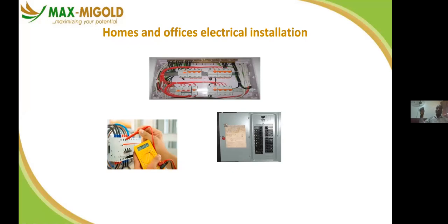And you see every breaker rated 5 amps, 10 amps, 32 amps, 50 amps, and so on. It also helps you not to overload a certain breaker. If you know the power rating of your appliance, like your electric kettle or your cooker in the kitchen, you cannot go on, maybe it's 50 amps. So you see 25 amps. A cooker is already placed on that 25 amps breaker, and you cannot go and load another thing onto it, because it will keep tripping and at the end of the day, the breaker will go bad. It helps you to evenly distribute your load in an electrical installation.